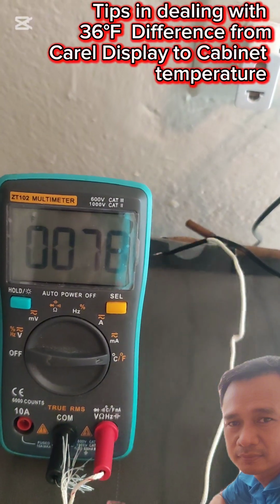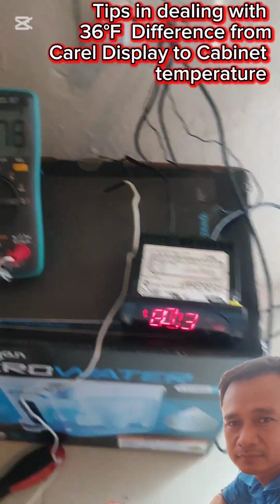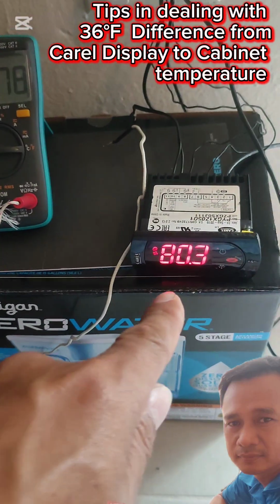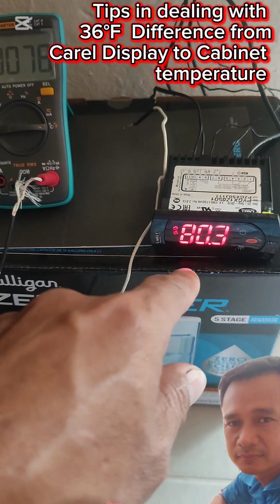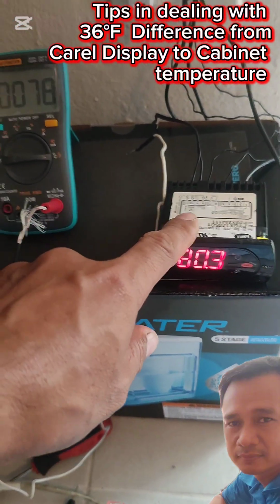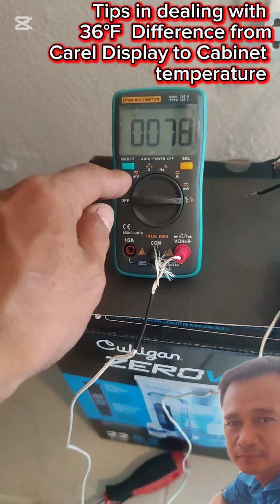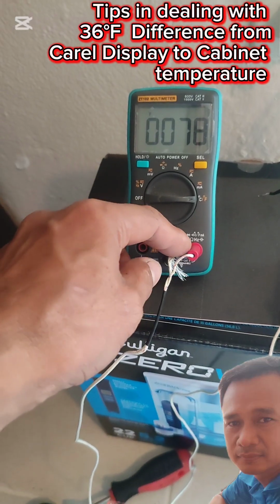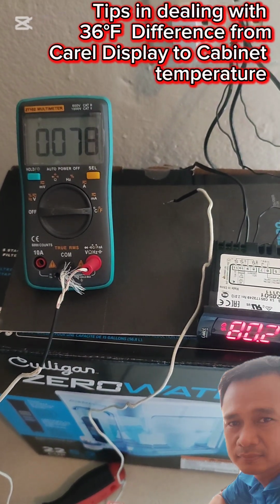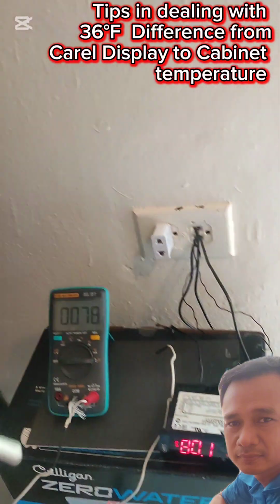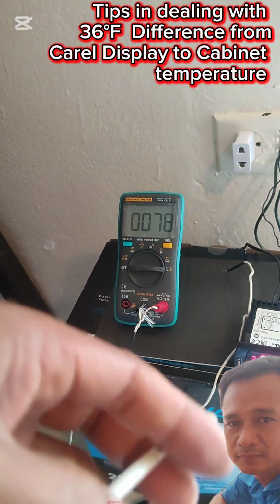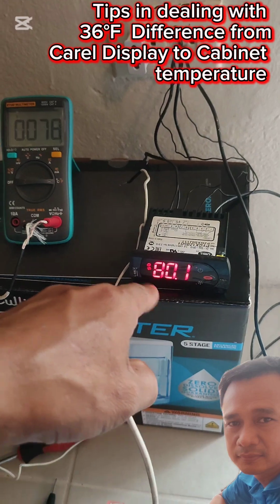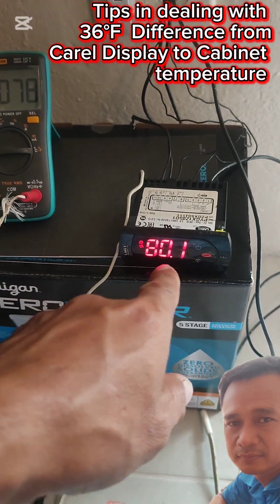So that's how you're going to troubleshoot, just in case you encounter a difference in the temperature from your controller to the measuring device that you're going to use in order to calibrate the unit or the refrigerator. And this is the culprit, so you don't need to calibrate this. Carel easy, and that's the model.